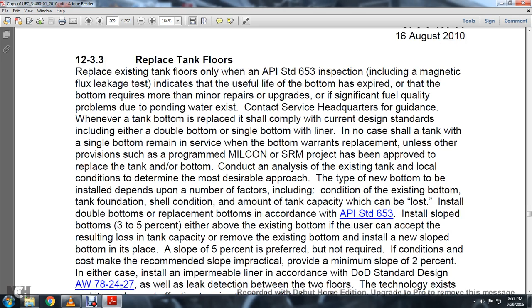Install the double bottom replacement in accordance with API Standard 653. Install the sloped bottom either above the existing bottom, if the user can accept the resulting loss of tank capacity, or remove the existing bottom and install the new sloped bottom in its place. A slope of 5% is preferred, though not required. In conditions where cost makes the recommended slope impracticable, provide a minimal slope of 2%.